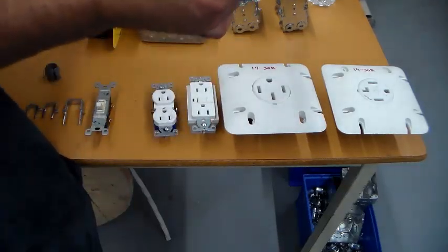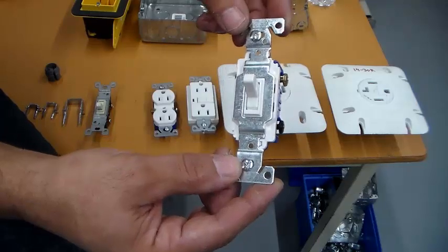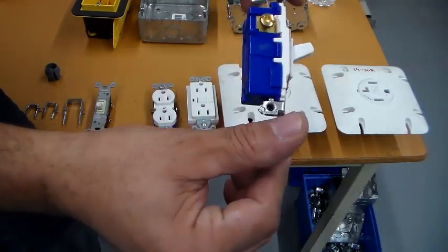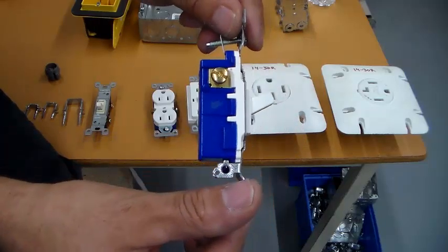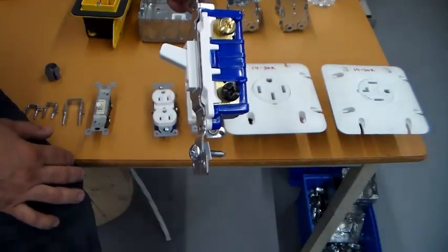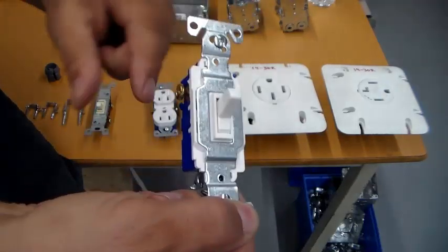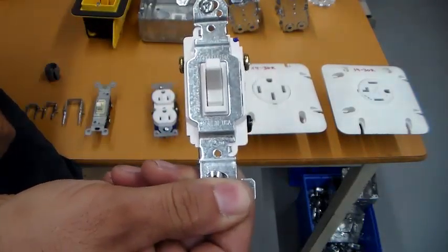In the three-way switch, you'll notice that there are screws on both sides. There's two brass screws on the top, and a black screw at the bottom. The black screw indicates the common point of the three-way switch. The two travelers in a 14/3 wire go on the brass screws.